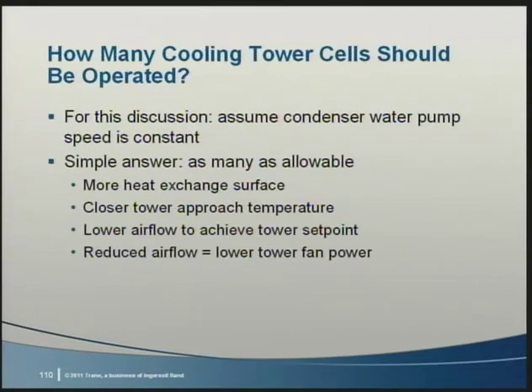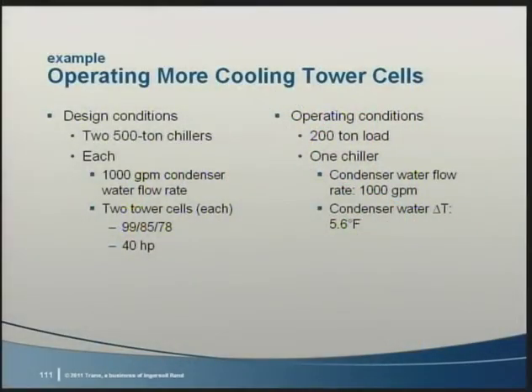Let's look at an example of operating more cooling tower cells. Here, we have 2 500-ton chillers selected at design conditions, each with a 1,000 GPM condenser water pump. A cooling tower is selected, and it has 2 cells, each with a 40 horsepower fan. At this point in time, there's a 200-ton load and one chiller is operating. This results in a 5.6 degree condenser water delta T. For this discussion, we set the condenser water flow at design flow of 1000 GPM for the single chiller.